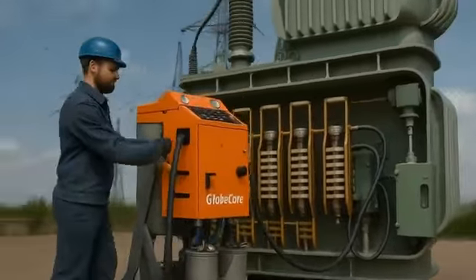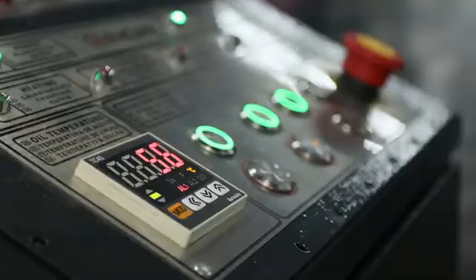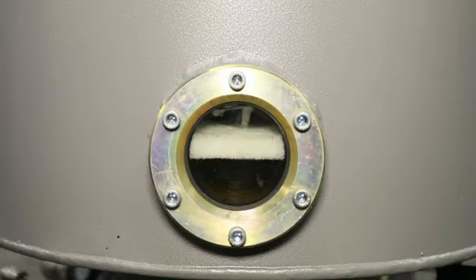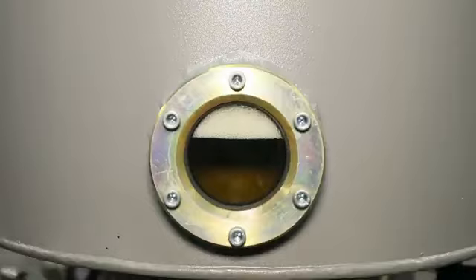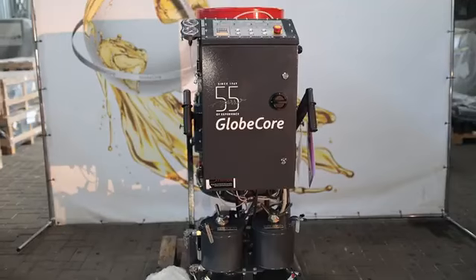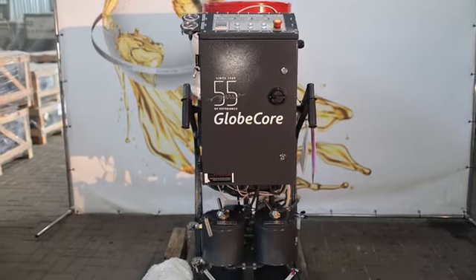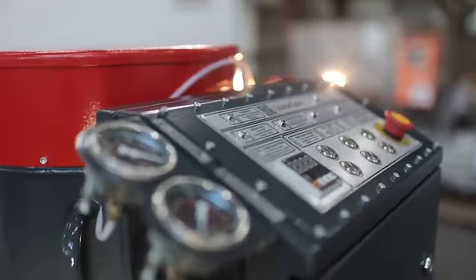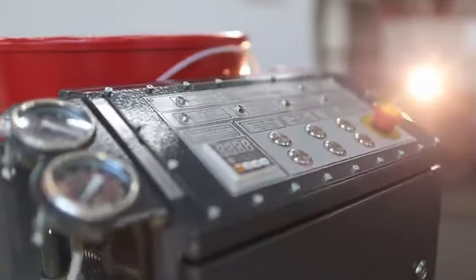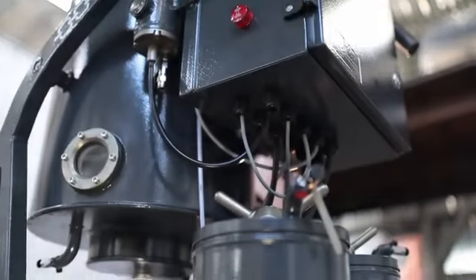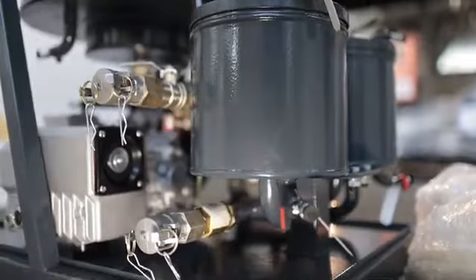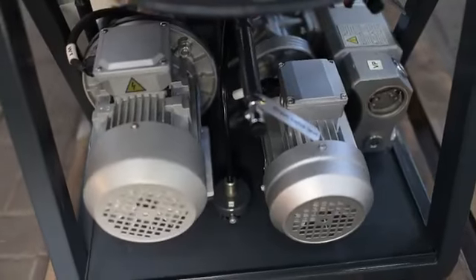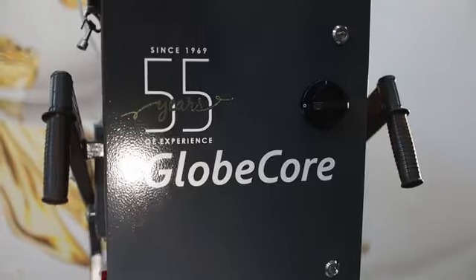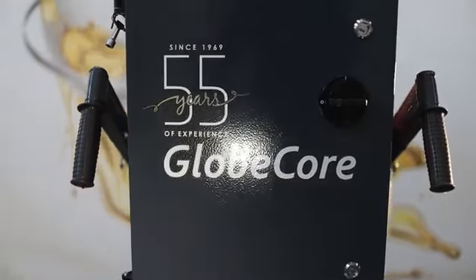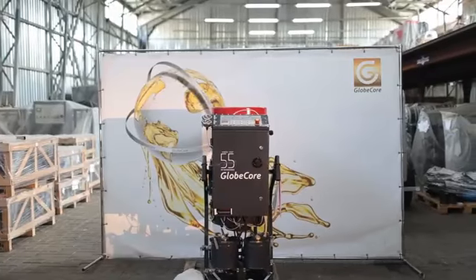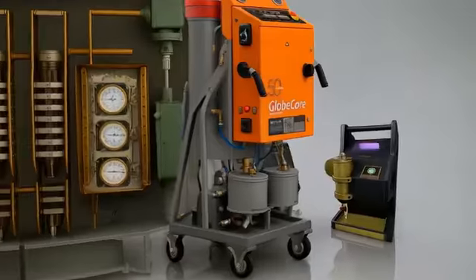Breakdown voltage increased up to 60 kV. Moisture content reduced to at least 10 parts per million. A special system for protection against foaming, which is very likely to occur during water cut oil processing. An oil leak sensor available. In case of leaks, the plant automatically stops running and alerts the operator to that effect. Noiseless operation. Ability to connect to a standard power outlet. Thus, the GlobeCore technology ensures comprehensive maintenance of onload tap changer oil systems, enhances their operational reliability, and extends their service life.